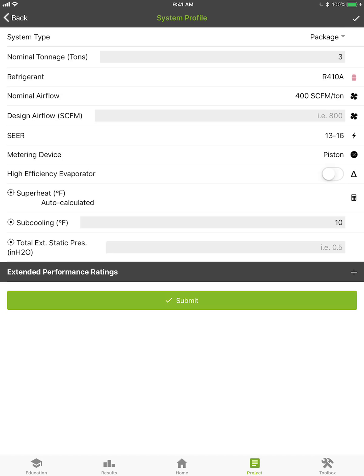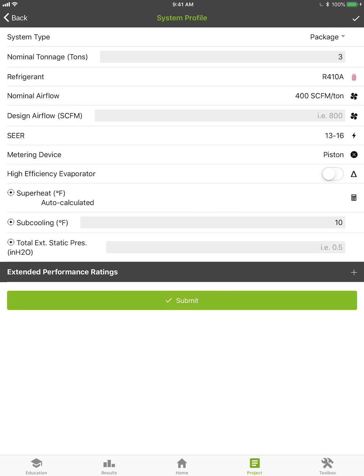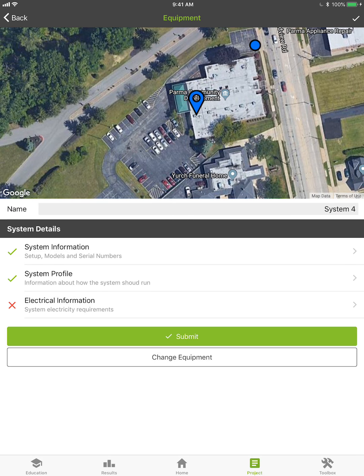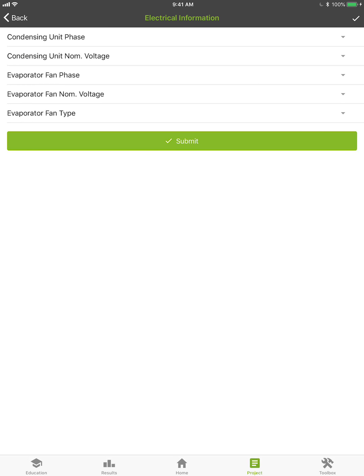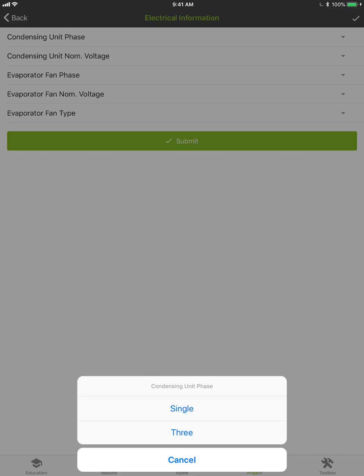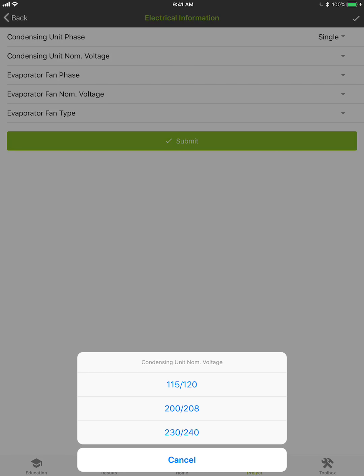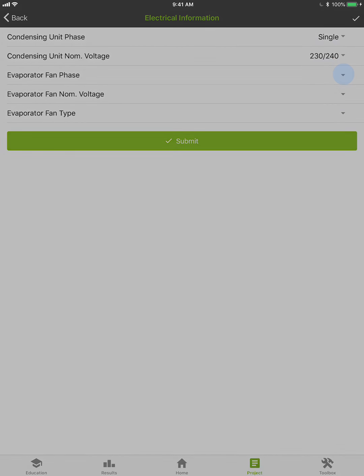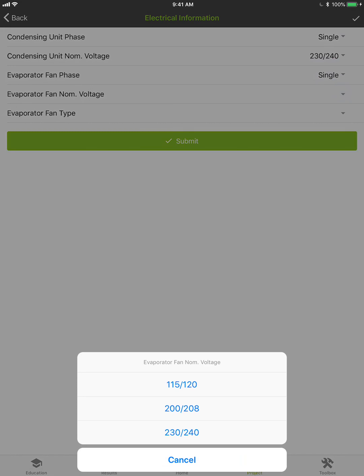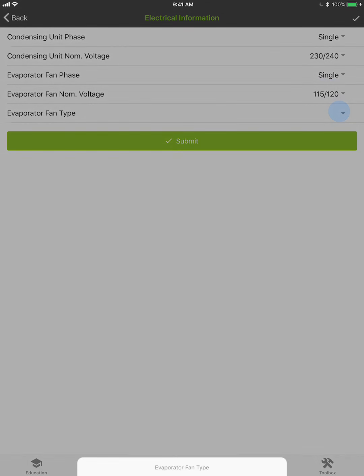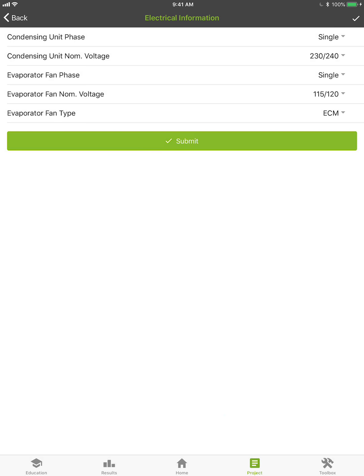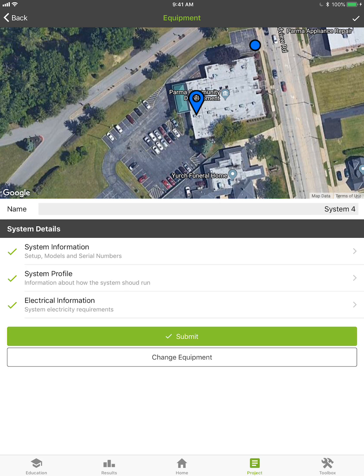The subcooling range is wider than the default — 10 is just the center of the range. If you have extended performance ratings you can add those in, but it's not necessary if you don't know them. Hit Submit. For electrical information it's a condensing unit — single phase, 230/240V. Evaporator fan is single phase, 115V, and evaporator fan type I'll select ECM. Hit Submit, and now all the profile information about that system is stored with that pin.